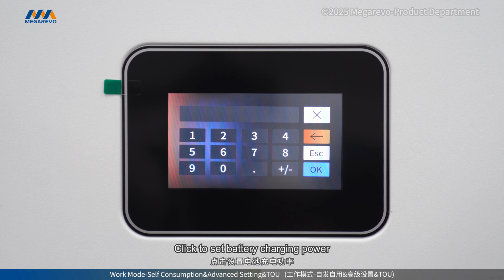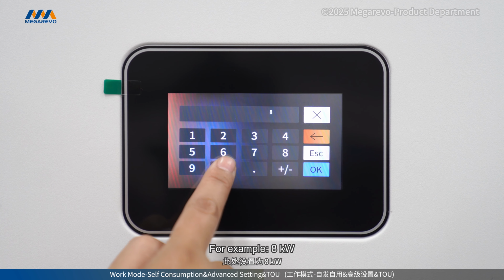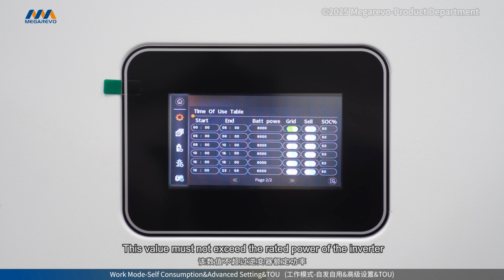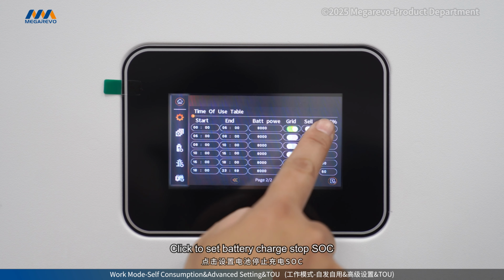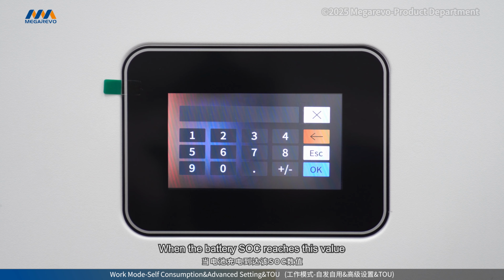Click to set battery charging power. For example, 8 kilowatts. This value must not exceed the rated power of the inverter. Click to set battery charge stop SOC. When the battery SOC reaches this value, charging stops. For example, set as 100%, meaning charging stops when the battery is full. Click Grid Power Limit to set the grid charging limit under TOU mode. For example, 5 kilowatts. Low SOC charge.